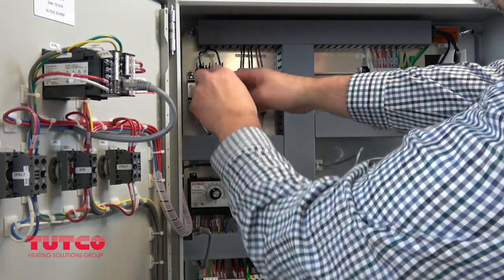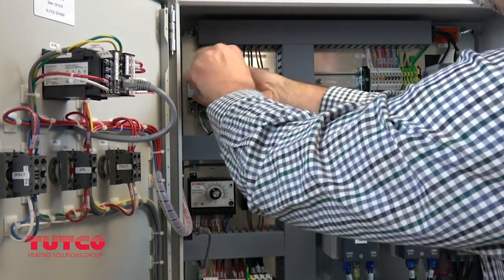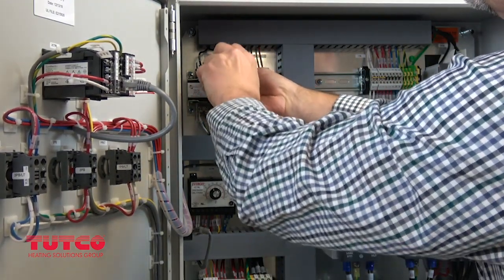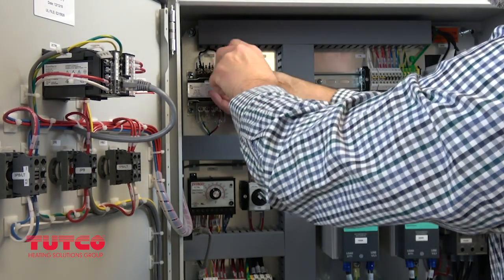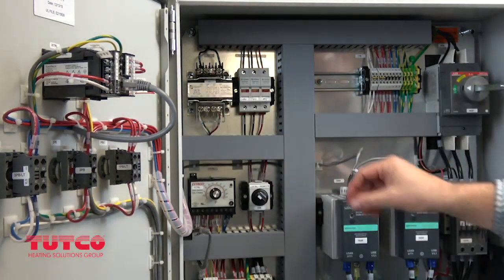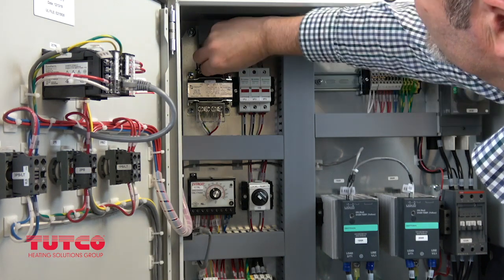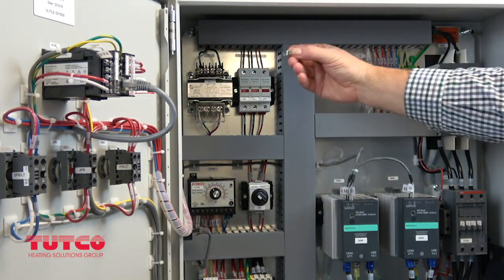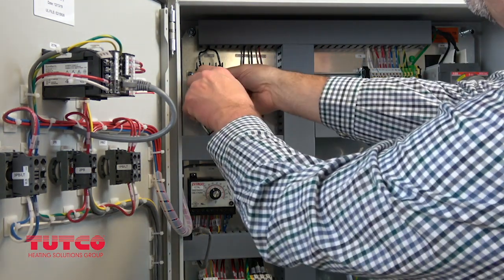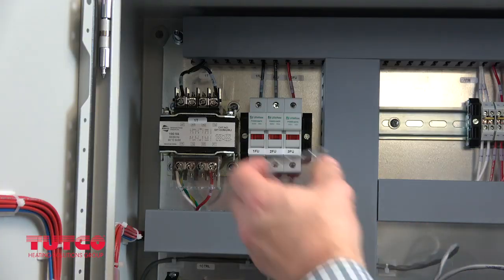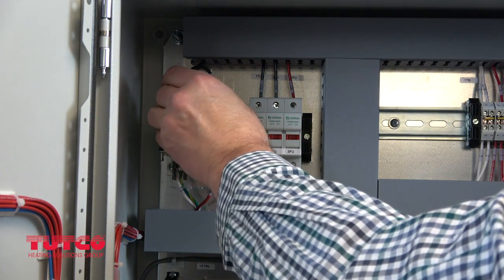For 240 volt input wiring, the jumper should be connected between 1 and 3, open between 3 and 2, and then connected again between 2 and 4. Remove the existing clip by loosening the screws. The jumper will easily be removed without entirely loosening the screws. Don't forget to add the finger safe cover back on when done.